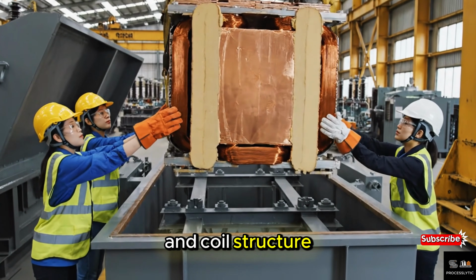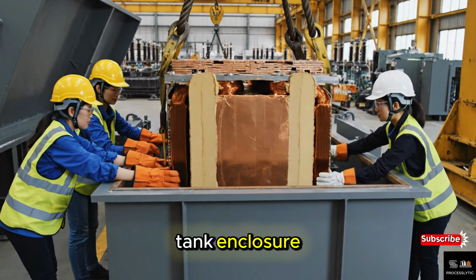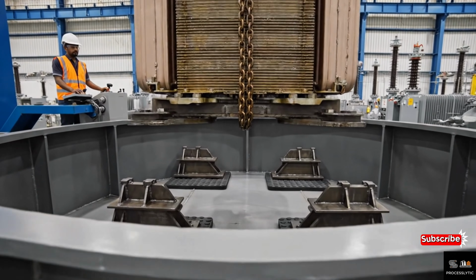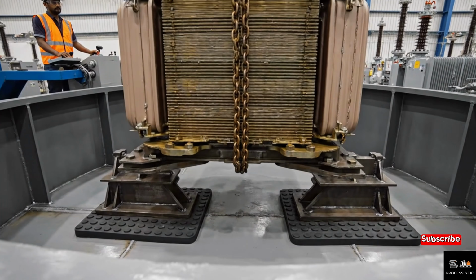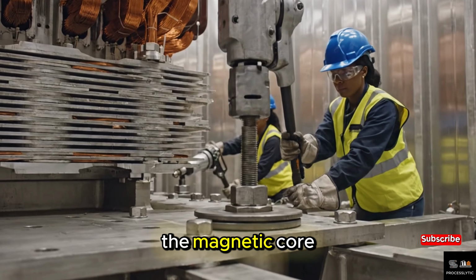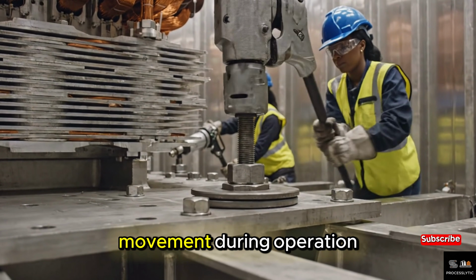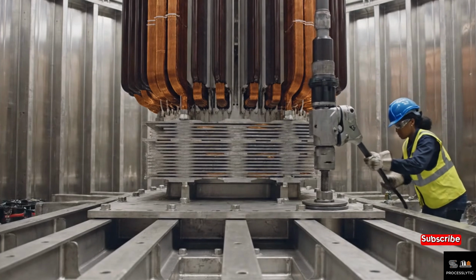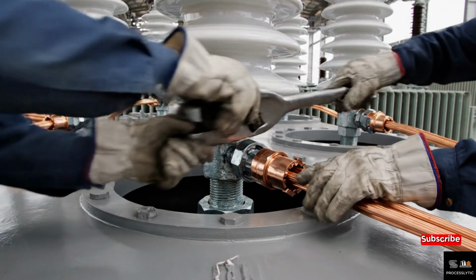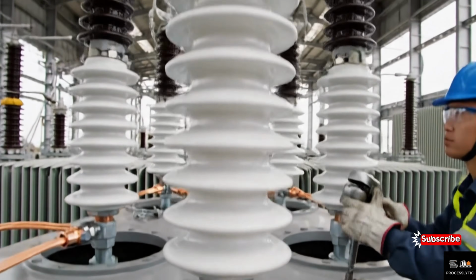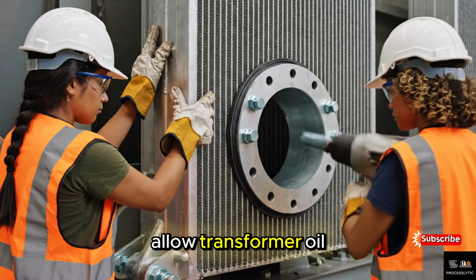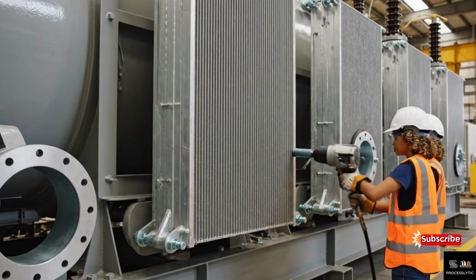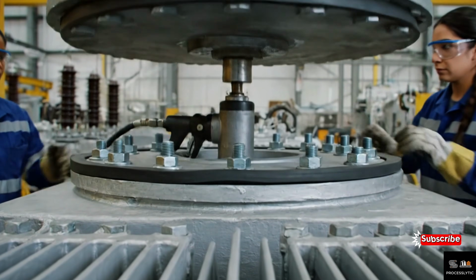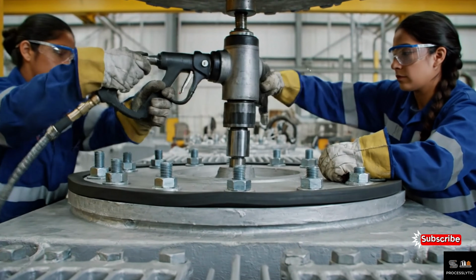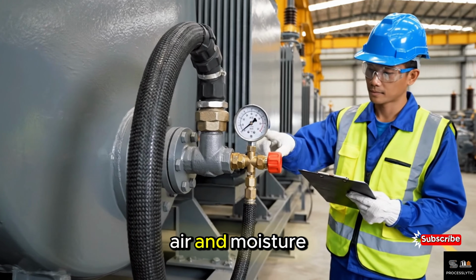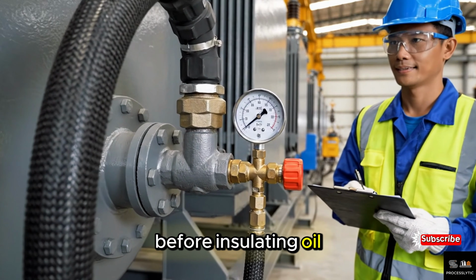The assembled core and coil structure is positioned inside the transformer tank enclosure. The magnetic core assembly is bolted securely to prevent internal movement during operation. External radiator panels allow transformer oil to circulate and dissipate operational heat. Air and moisture are removed from the sealed tank before insulating oil is introduced.